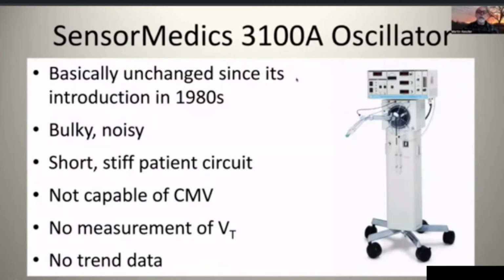All right, moving to high frequency combined with volume guarantee. Well, the SensorMedics can't do that. The SensorMedics, unfortunately, is still the only high frequency device available in the United States. It is an antique. It hasn't changed in its basic functionality since the 1980s. It's bulky, it's noisy. It's got that stiff short patient circuit, so kangaroo care is problematic. It can't do anything other than high frequency, can't measure tidal volume, doesn't give you any waveforms, doesn't store any data.